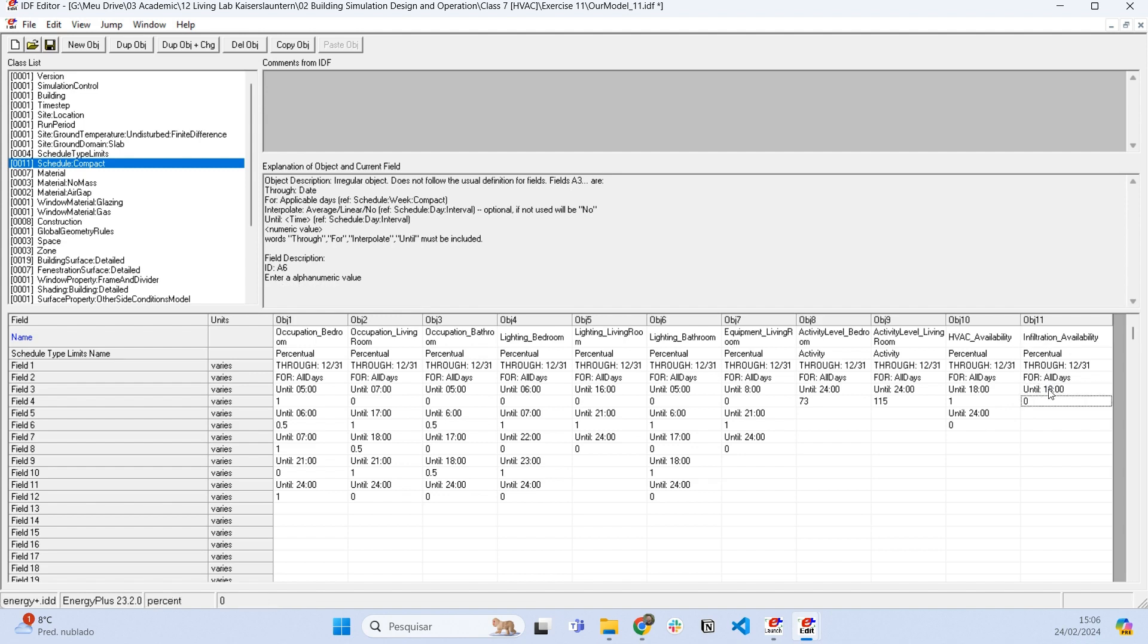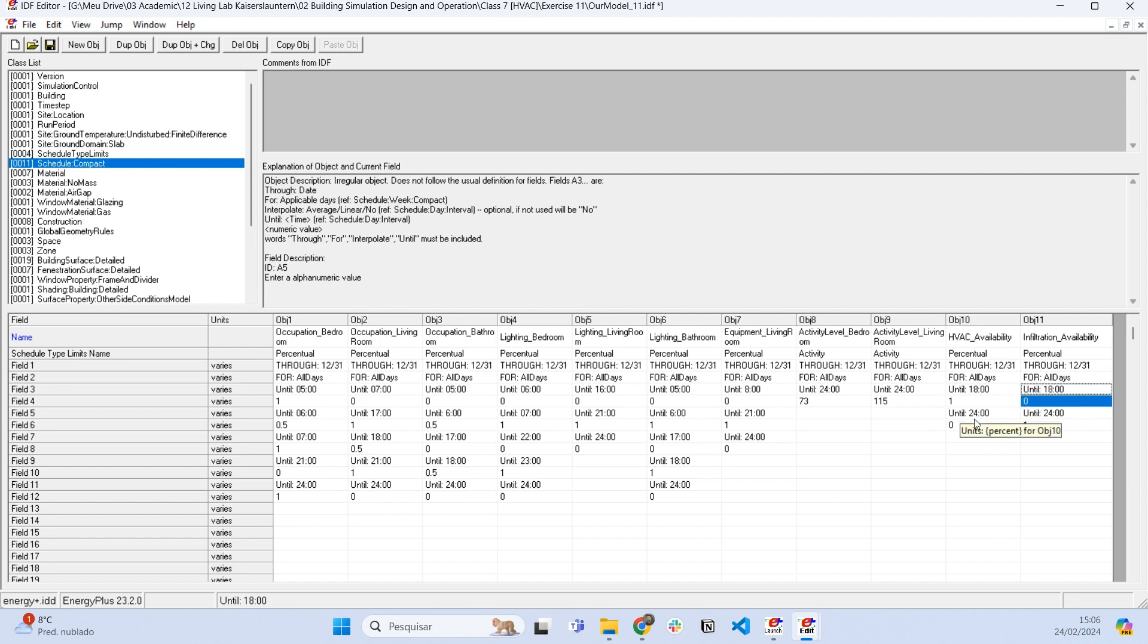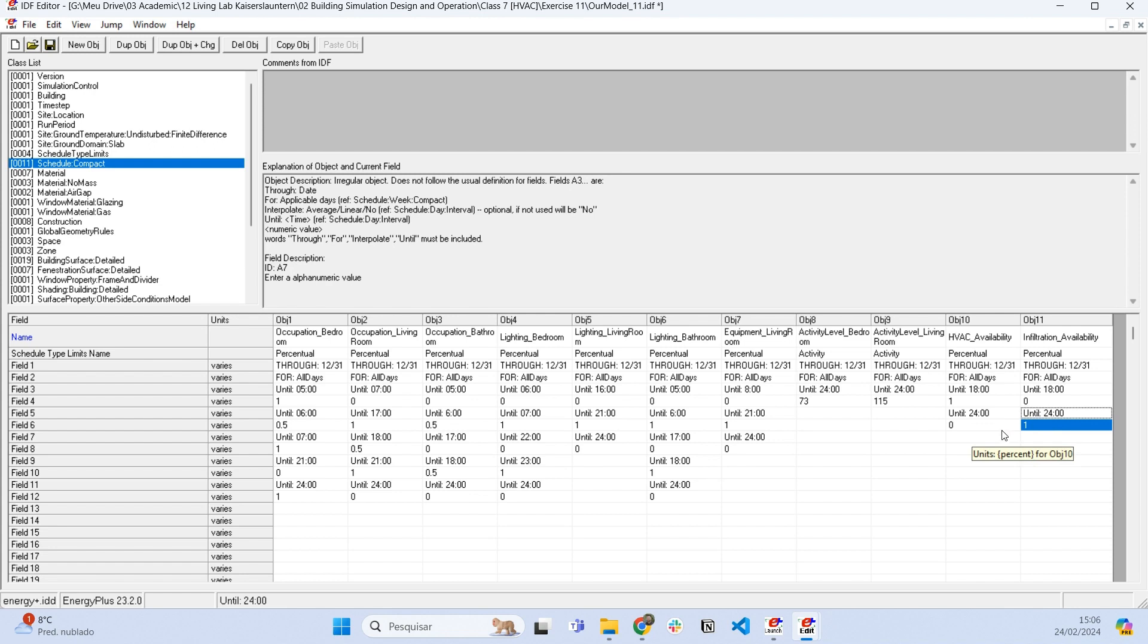Until 6 PM the infiltration is going to be zero, and until midnight it's going to be one. We are saying there is air conditioning until 6 PM and there is no infiltration because of the difference of pressure. There is no air conditioning until midnight and there is infiltration because there is no negative pressure to prevent the infiltration from happening anymore.